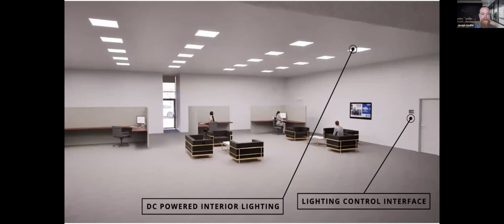So out in the lobby, we replaced the legacy fluorescent lighting with a fully DC powered 24-volt lighting system. These are high efficiency 2x2 troffers designed specifically for low voltage direct current. The result is exceptional lighting quality, zero flicker or glare, full dimming range, all while reducing the upstream conversion losses typical from AC lights, even AC LED lights.